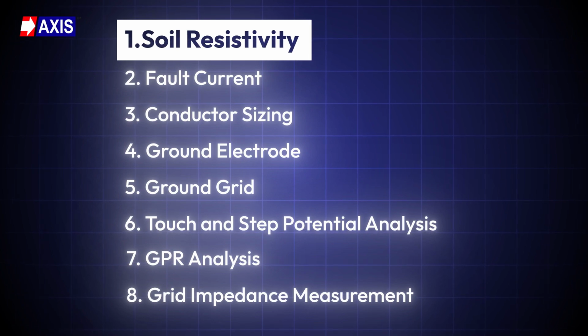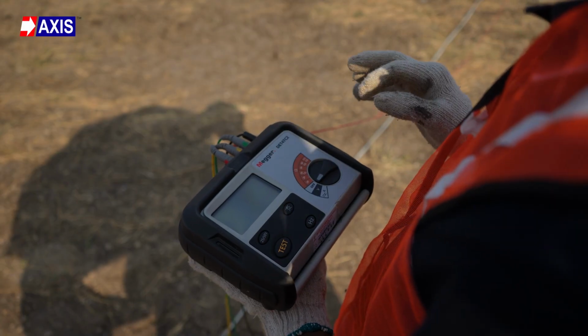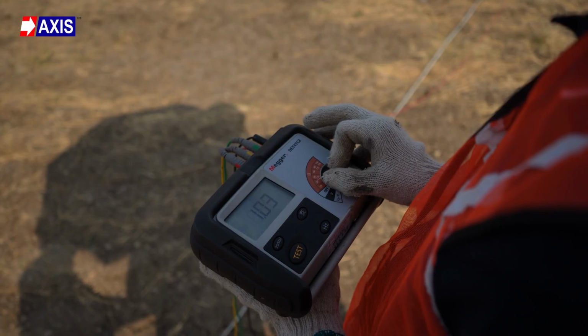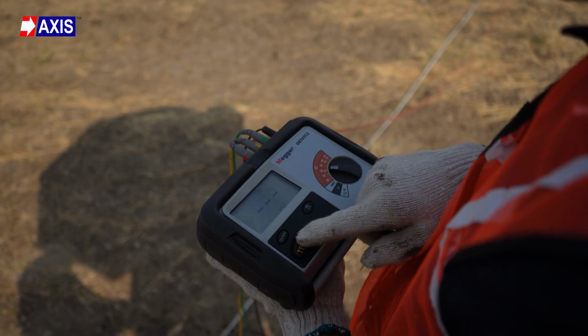The process follows 8 steps, and it starts with soil resistivity. Before any earthing system is designed, the first thing you must do is measure resistivity at the site. So what exactly is soil resistivity? It is the measure of how strongly the soil opposes the flow of electrical current. The lower the resistivity, the easier it is for the current to flow into the earth, making your earthing system more effective. The higher the resistivity, the harder it is for the current to dissipate and the more difficult it is to achieve a safe earthing design. If soil resistivity is not measured accurately, the entire earthing design will be built on wrong assumptions.